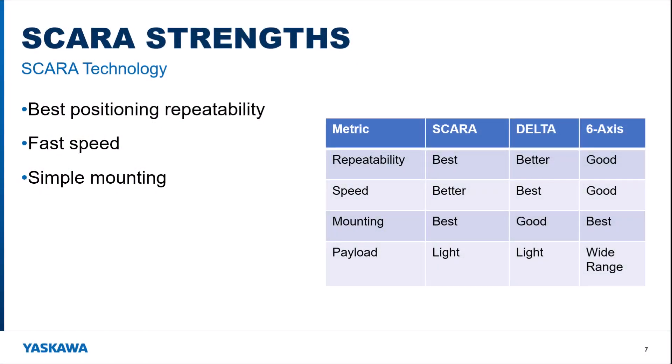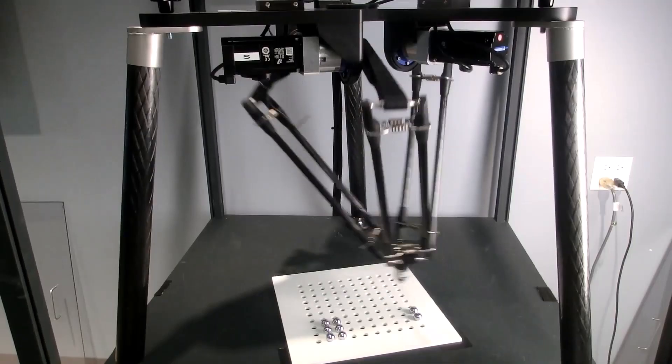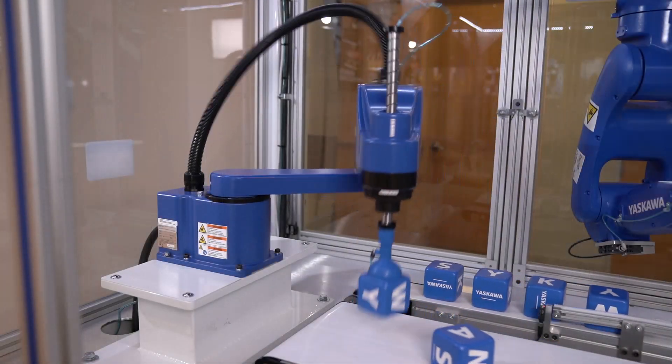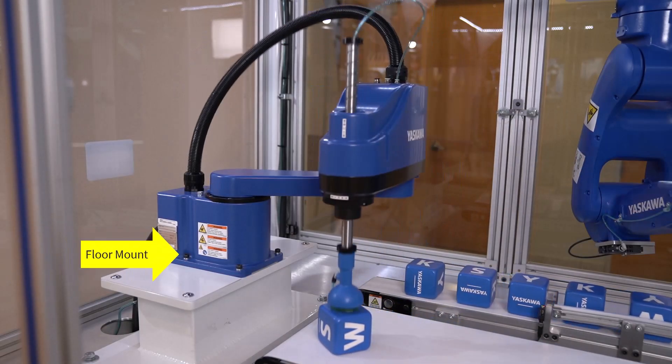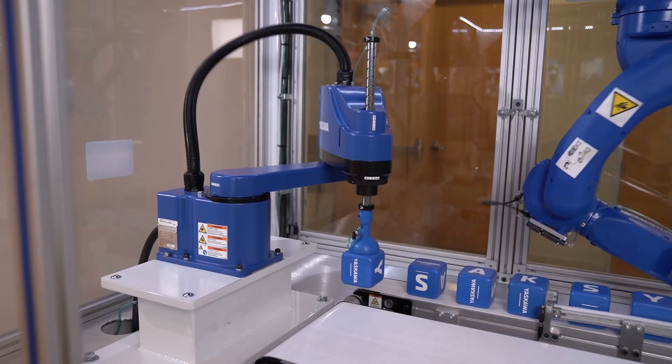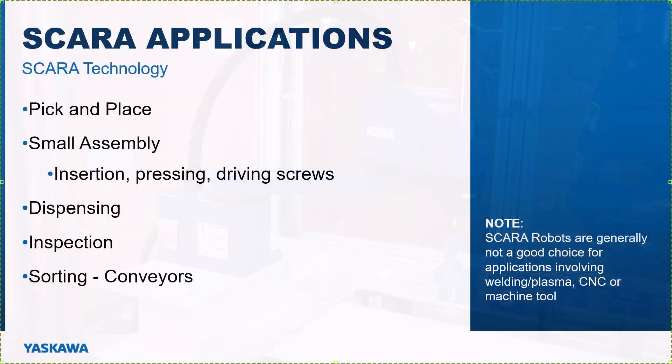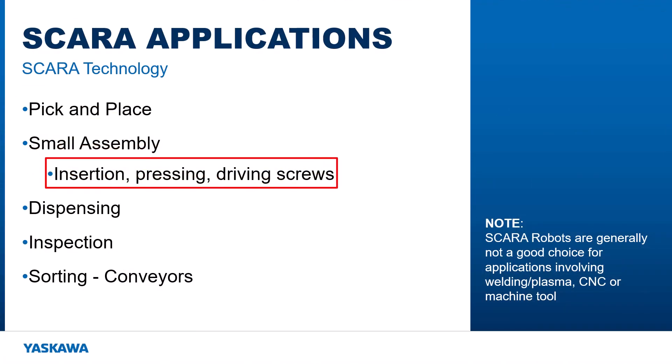This table summarizes the SCARA robot compared to other articulated robot mechanisms. The SCARA has the best repeatability of all articulated robots. And while a Delta robot is still a faster way to move light loads, the SCARA can be bolted down with a simple floor mount rather than an overhanging structure. These characteristics make SCARA a great choice for fast pick and place of small parts with high repeatability. The same applies to assembly processes involving small part insertion, pressing, or even driving screws with the rotational axis.